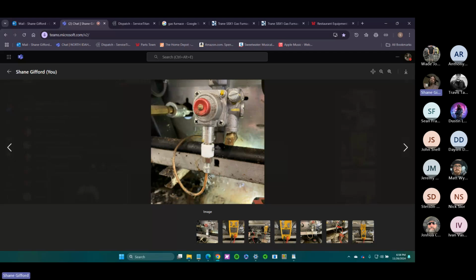Now that we're on the topic of diagnosing stuff, the most common kind of failure in any heating appliance is the thermocouple, because nobody thinks about cleaning it or maintaining it. But honestly, if you're working on a hot side appliance and you've got the NTE to cover it, even if that's not part of the problem, pull the pilot assembly out and clean the thermocouple. But before you make a change, record your data. Do a before and after on the thermocouple. And that's another thing you can tell your customer: while I was here, I pulled the thing out and cleaned it. Now you're reading better, and it'll last longer.